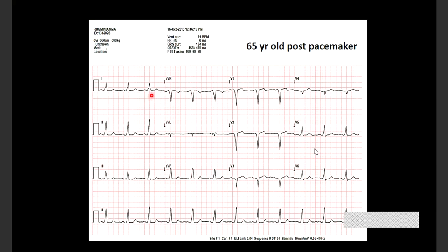So, if you don't see spikes, one reason might be the patient is having intrinsic activation. Another reason might be the patient is programmed to a bipolar mode, which is very, very common. And the third reason may be abnormal filter settings. If the low pass filter is really low, 30 hertz or 40 hertz, traditionally instead of the routine standard 100 hertz or something like that, you might not see the spikes.